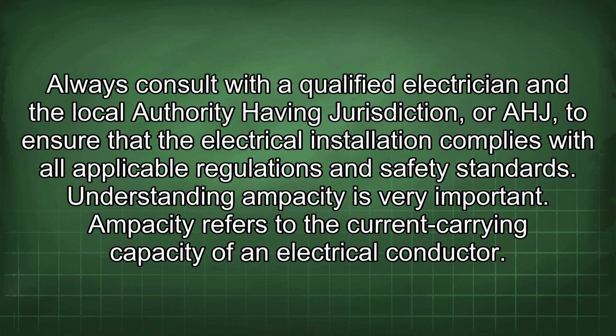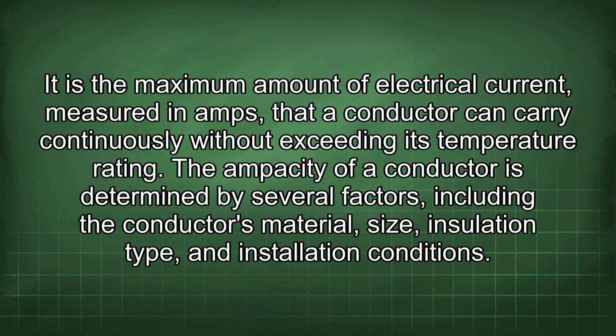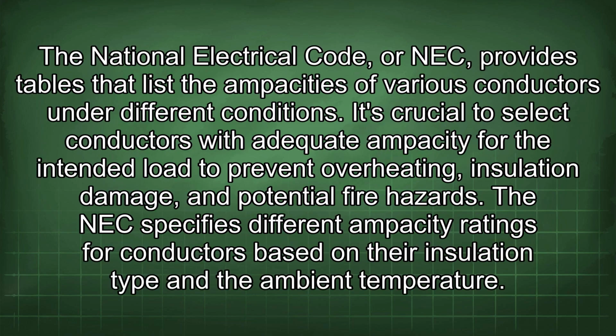Understanding ampacity is very important. Ampacity refers to the current carrying capacity of an electrical conductor. It is the maximum amount of electrical current, measured in amps, that a conductor can carry continuously without exceeding its temperature rating. The ampacity of a conductor is determined by several factors, including the conductor's material, size, insulation type, and installation conditions. The National Electrical Code, or NEC, provides tables that list the ampacities of various conductors under different conditions.